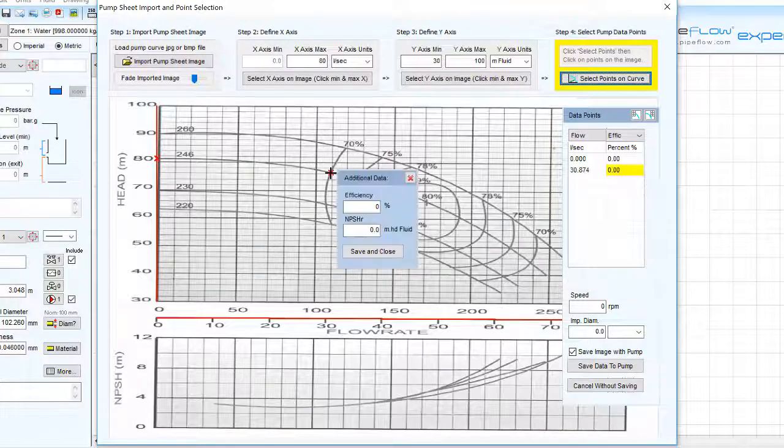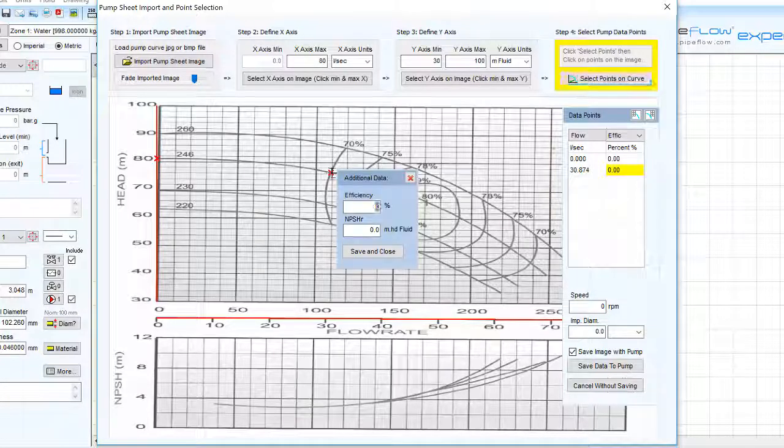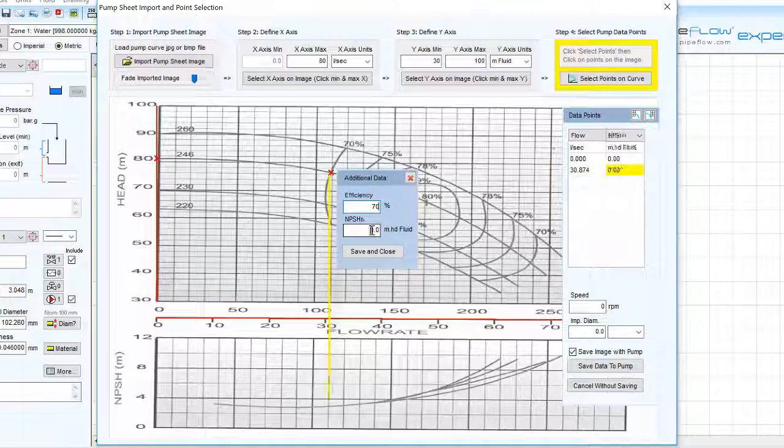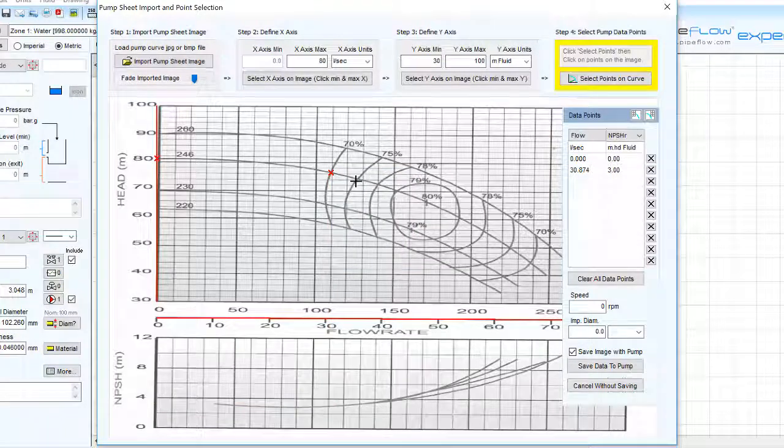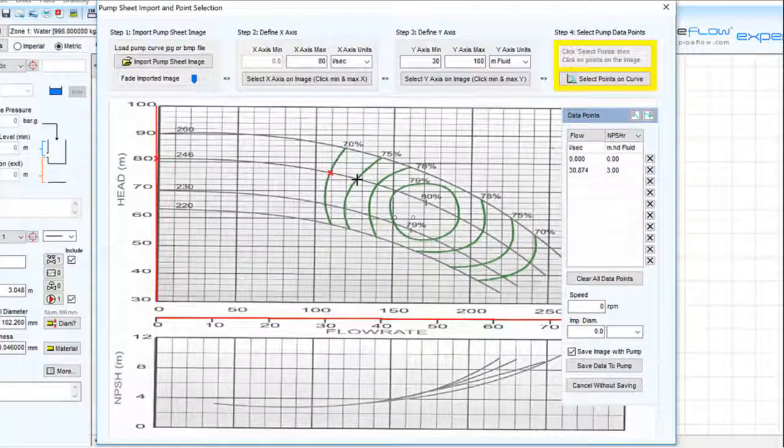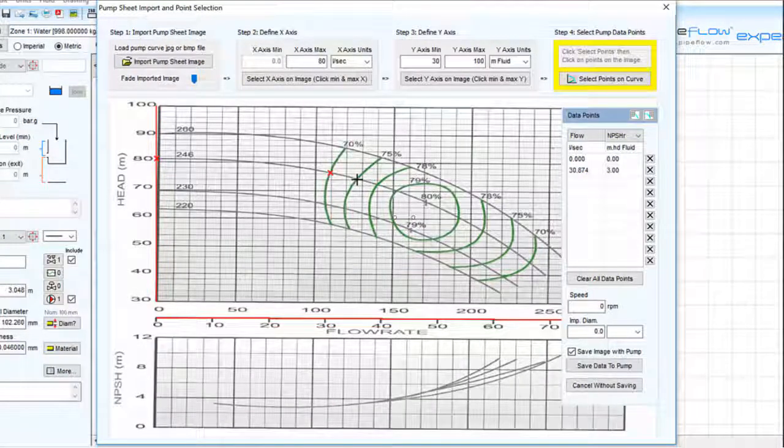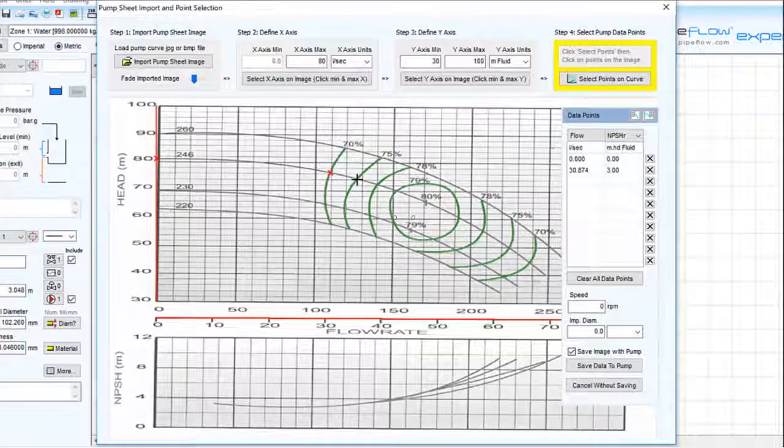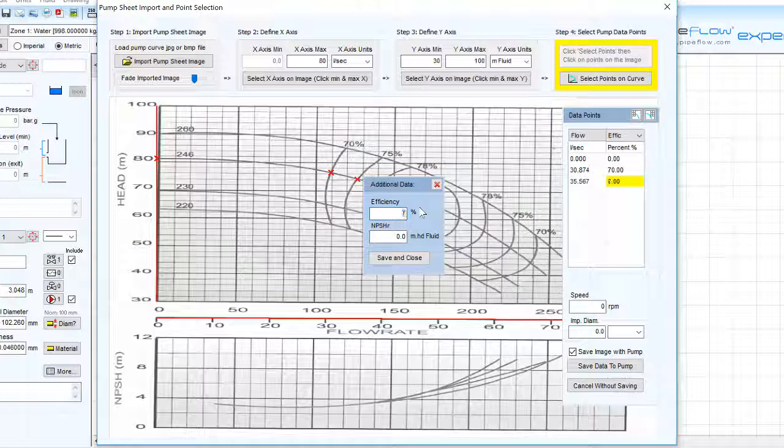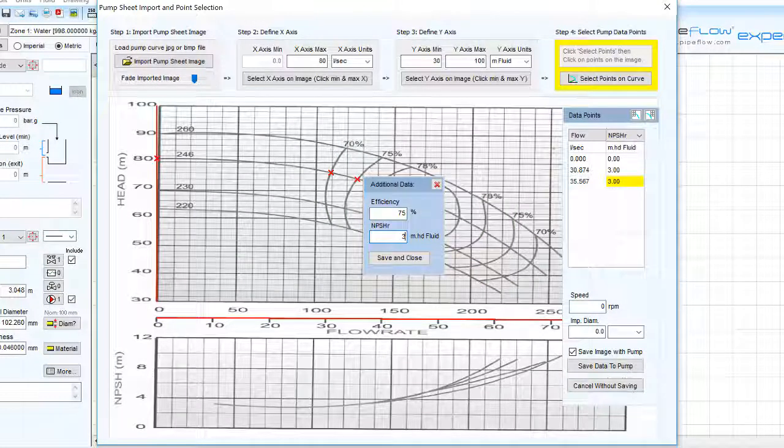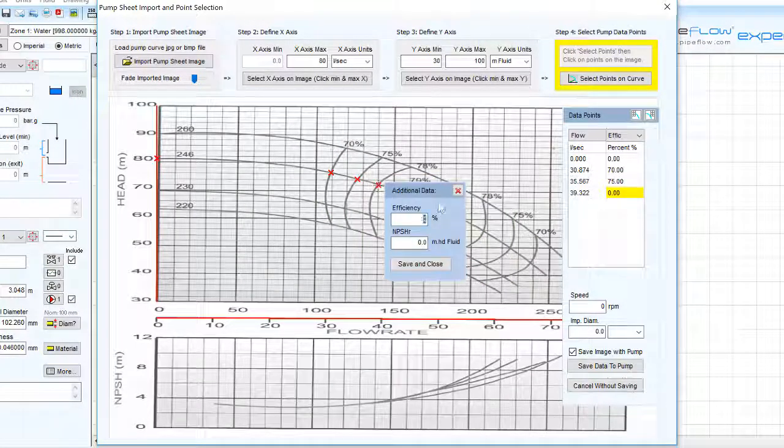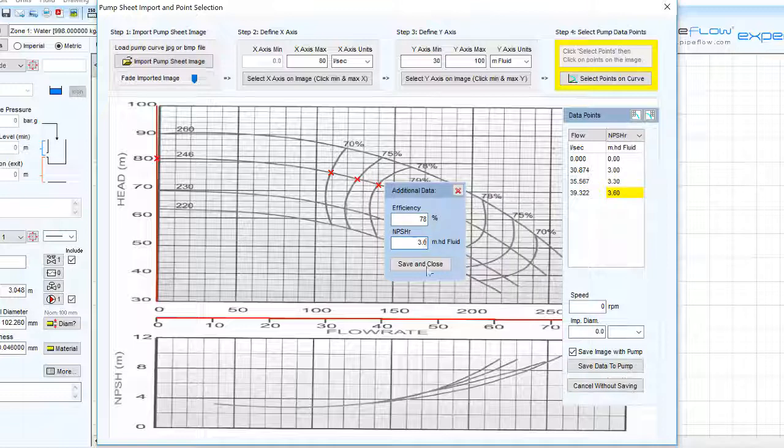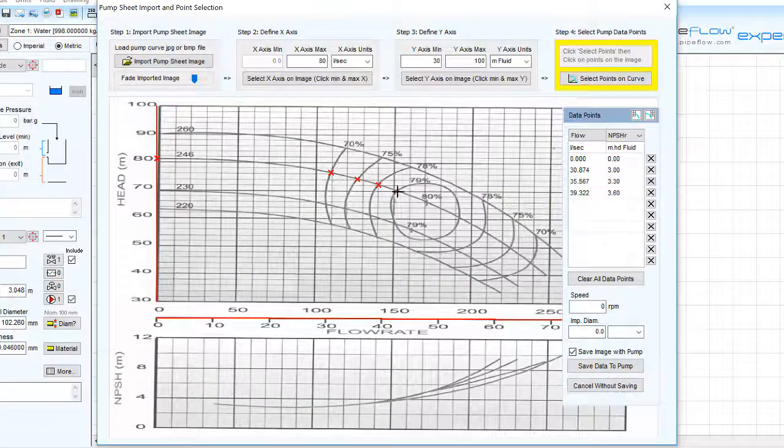As we select points, we are asked to enter the efficiency and NPSHR associated with each operating point. With this in mind it is a good idea to choose points that intersect with efficiency curves. You can build up the pump model by repeating this to add up to 10 points.